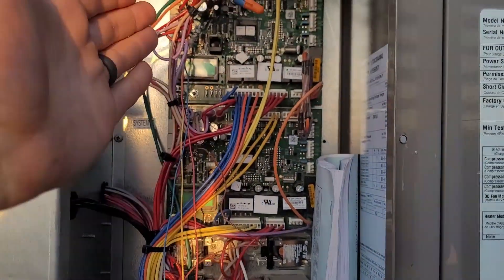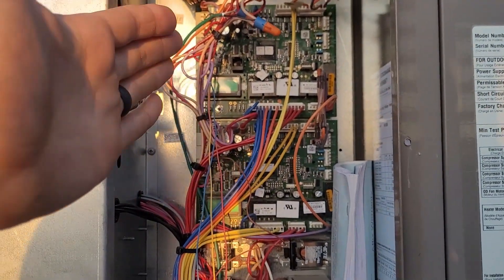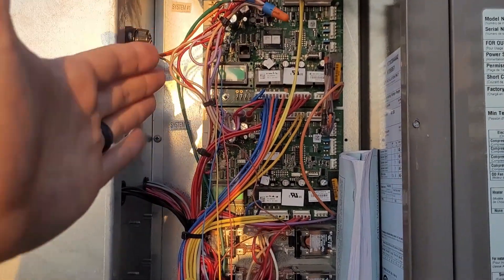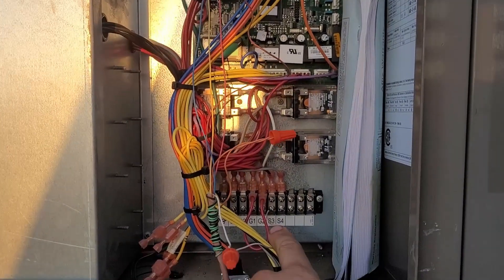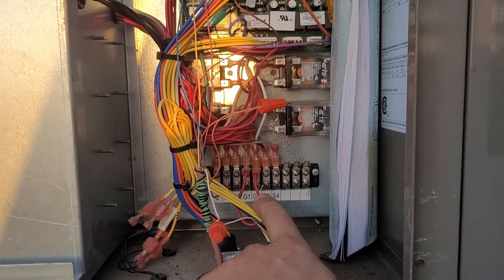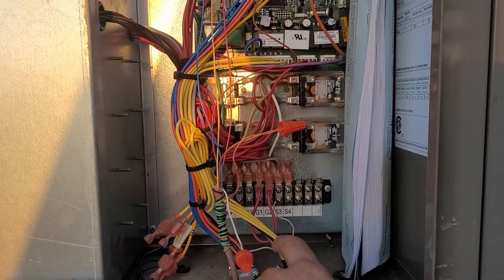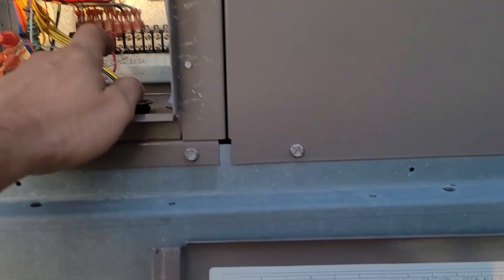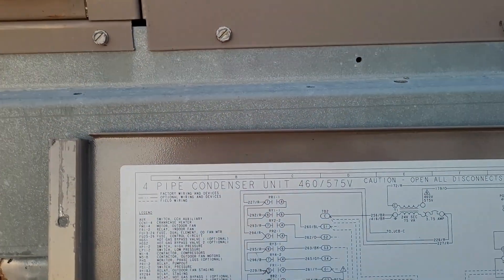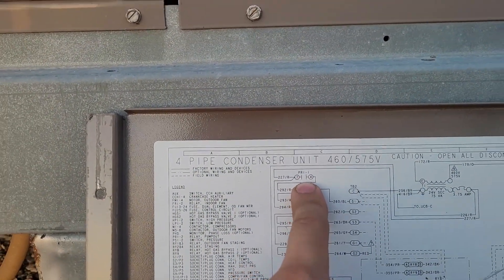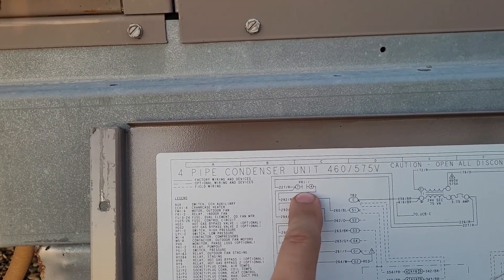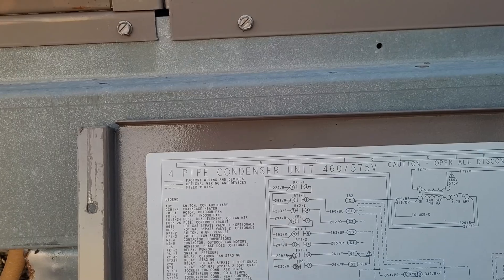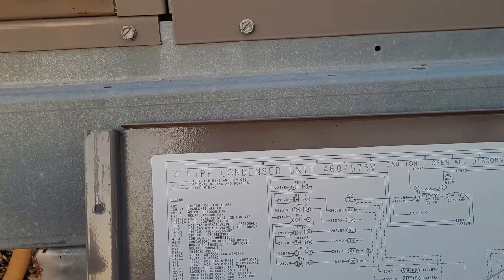So your calls come up, and then the board makes a decision and sends a signal back down to the liquid-line solenoid when it wants it to open. And based on what the board wants and what this pump-down, pump-out relay is doing, the liquid-line solenoid is either open or closed. So that all makes sense.